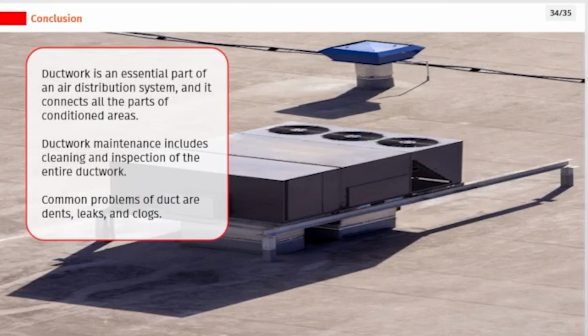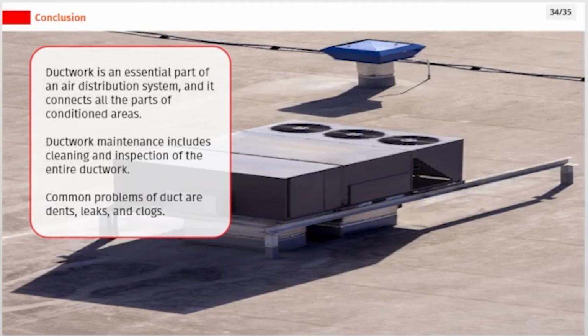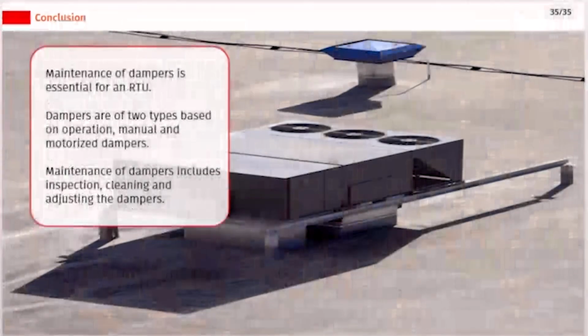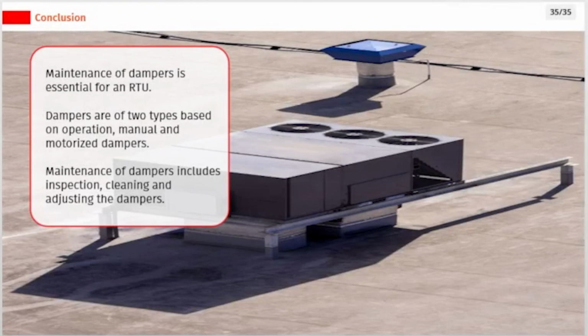Ductwork is an essential part of an air distribution system, and it connects all the parts of conditioned areas. Ductwork maintenance includes cleaning and inspection of the entire ductwork. Common problems of ducts are dents, leaks, and clogs. Maintenance of dampers is essential for an RTU. Dampers are of two types based on operation: manual and motorized dampers.